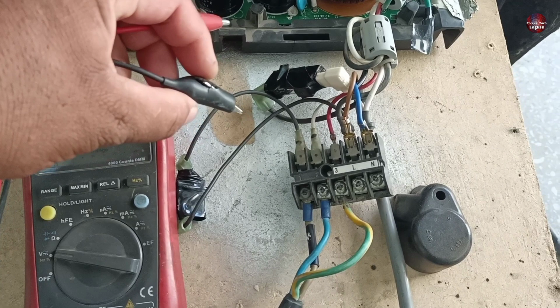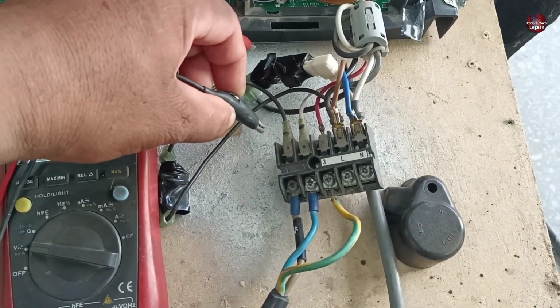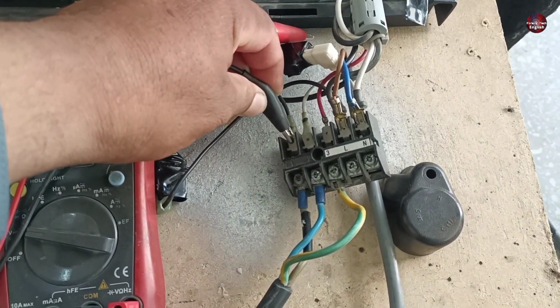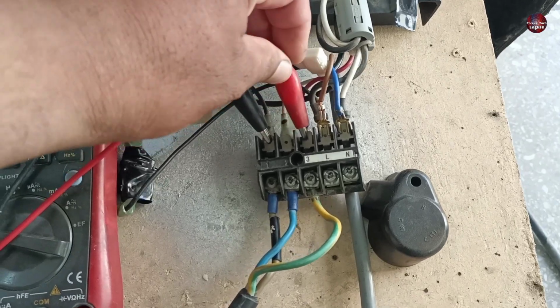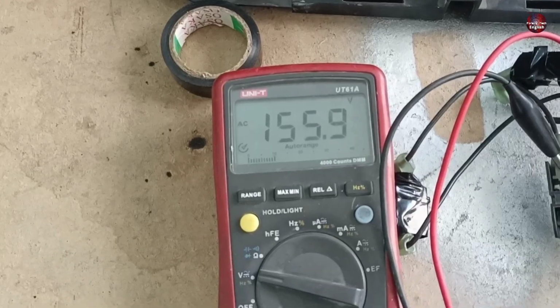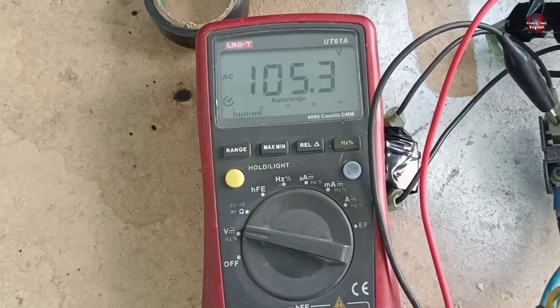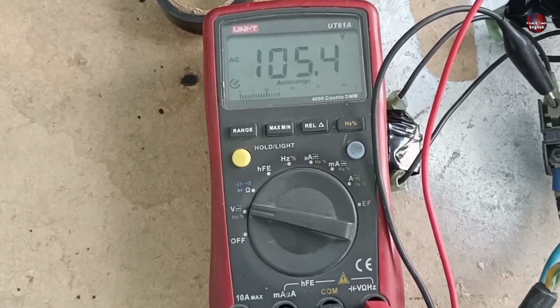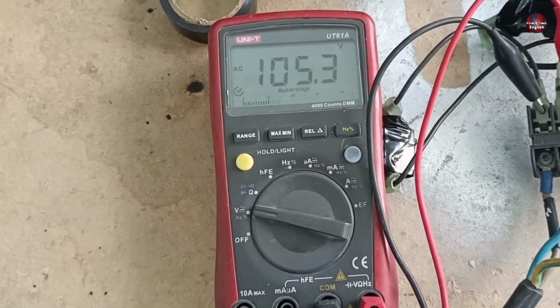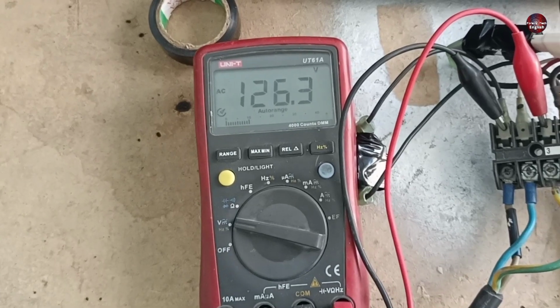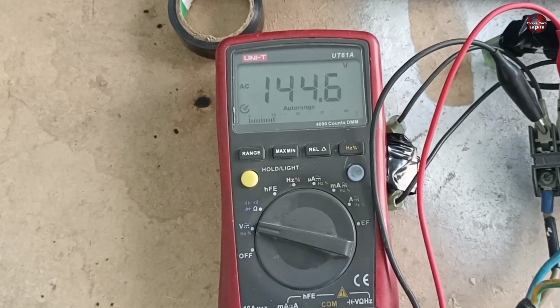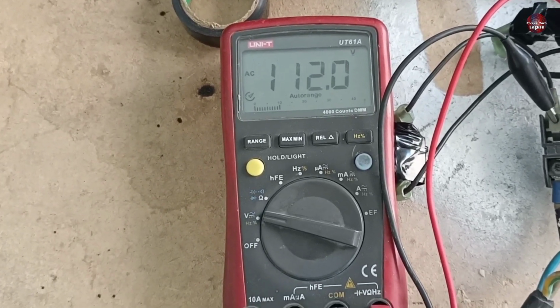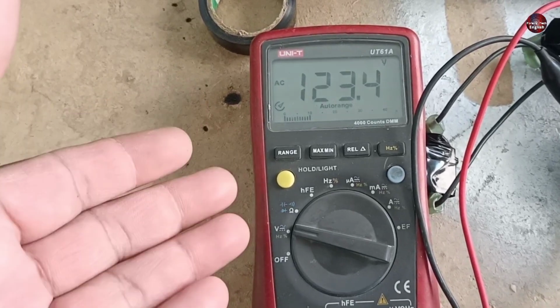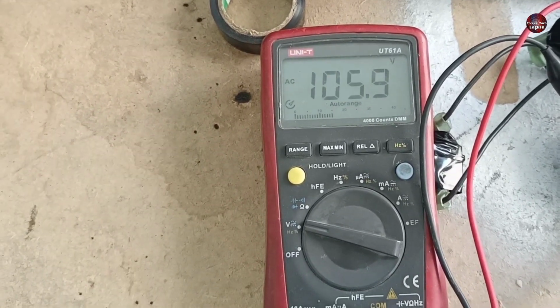Next I will check the communication of this motherboard. I will attach the black probe to neutral and the red probe on the third communication terminal. High voltages pass through the communication line in Fujitsu units, and it can be checked on both AC and DC volts. I am checking it on AC since high voltages pass through the AC line. The voltages fluctuate on the multimeter, which means both the indoor and outdoor motherboards are communicating with each other.